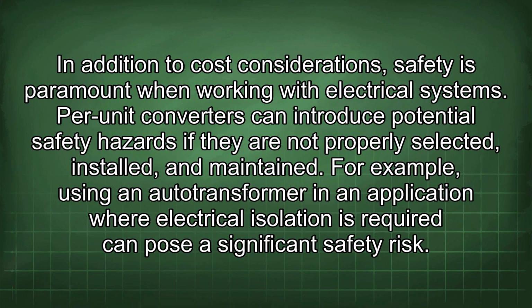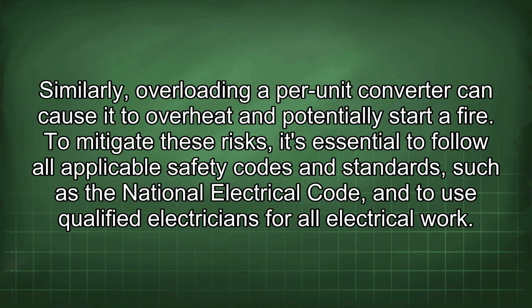In addition to cost considerations, safety is paramount when working with electrical systems. Per-unit converters can introduce potential safety hazards if they are not properly selected, installed, and maintained. For example, using an auto-transformer in an application where electrical isolation is required can pose a significant safety risk. Similarly, overloading a per-unit converter can cause it to overheat and potentially start a fire.